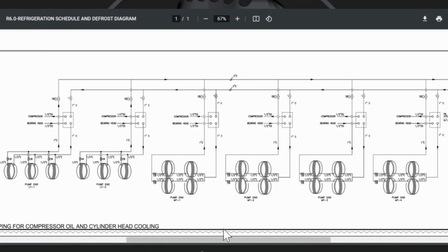Because then you don't have, let's just say, a nice 75-degree head on that one and then the other one adjacent all the way down. If you would have run in series, it would have been 180 degrees or whatever. So you're getting more constant head temperature across the board, which means your oil wear is going to be a lot more even, as well as probably bearing wear as well. Yeah. Everything is better the more even you can keep the temperature.